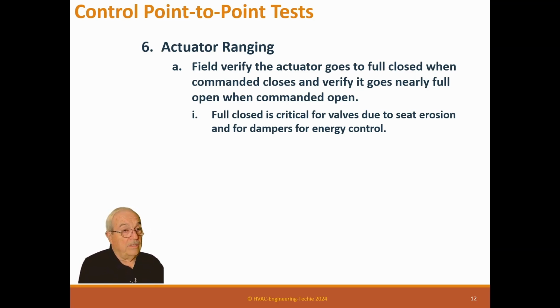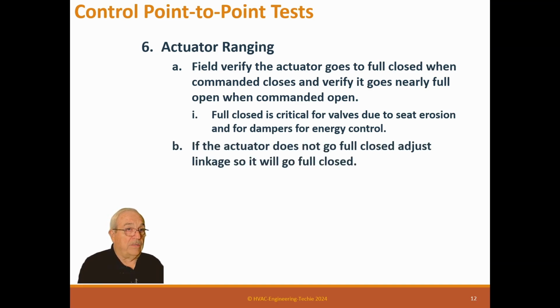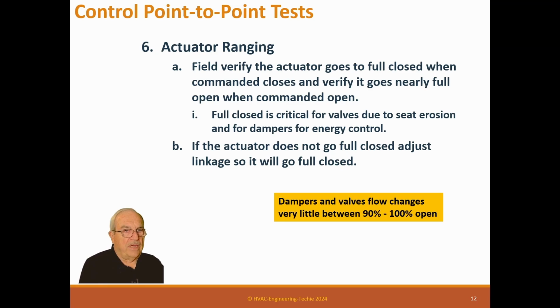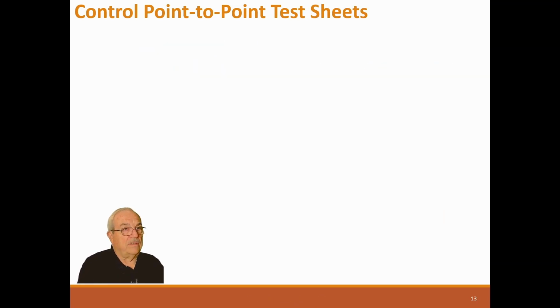How can you tell if it's full closed? Well, number one is you can listen to it, you can hear it, especially if you carry a field stethoscope with you, which I do, and you just listen to it, and if you hear flow through the valve, it's leaking by. You gotta solve that. There are other ways you can tell that it's flowing by, but that's a sure one if you can hear it. If the actuator does not go fully closed, adjust the linkage so it will go fully closed, and that's an easy linkage fix. And it'll probably affect how much it goes open, but it doesn't matter. Dampers and valve flow changes, very little flow between 90 and 100%. Very little effect. It's all down at the closed end.